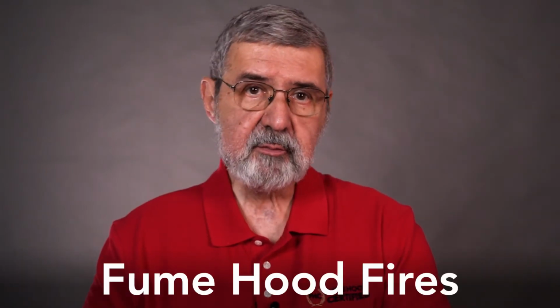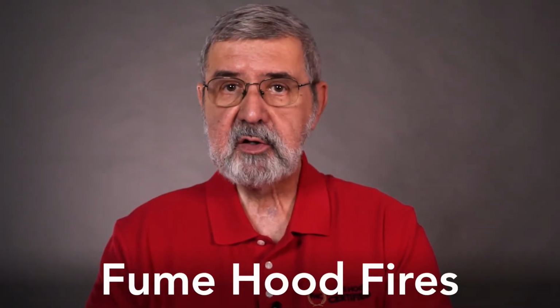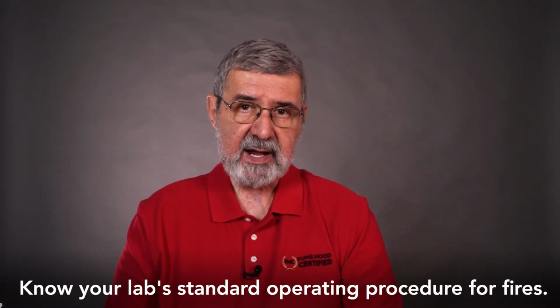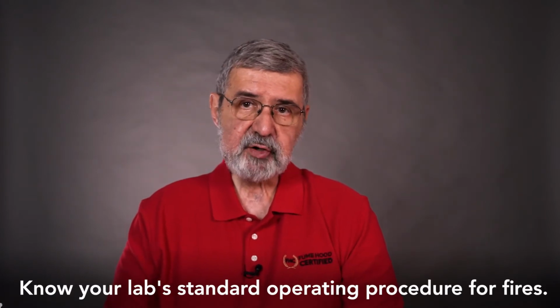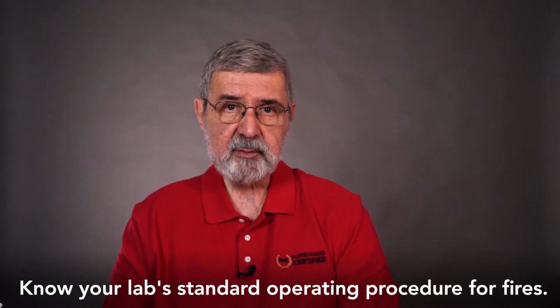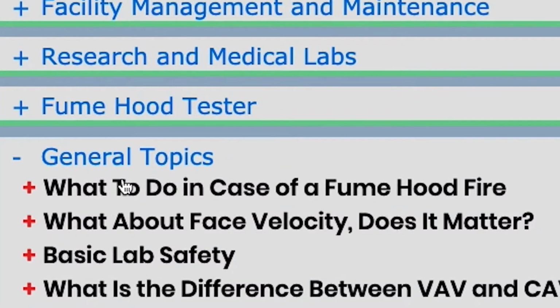While you might not have thought much about it, fume hood fires are another common hazard. While there are many reasons for fires, let's look at the role of the sash when a fire happens. In case of a fire, close the sash completely to minimize the amount of air feeding the fire. The sash also keeps the fire inside the hood and minimizes its spread. The proper action when a fire does occur varies. You need to understand the SOP of your lab and respond accordingly. This is a very complex topic that varies from lab to lab, and because of its complexity, we offer a training module that focuses just on fume hood fires.